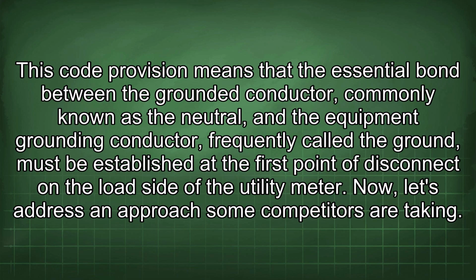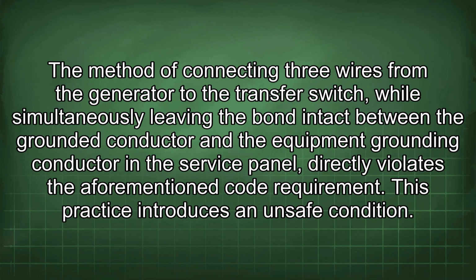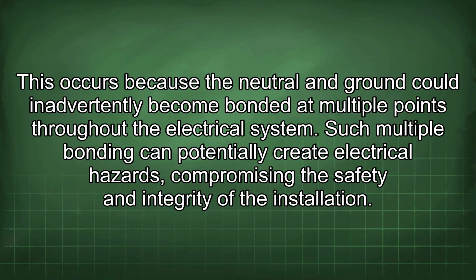Now let's address an approach some competitors are taking. The method of connecting 3 wires from the generator to the transfer switch, while simultaneously leaving the bond intact between the grounded conductor and the equipment grounding conductor in the service panel, directly violates the aforementioned code requirement. This practice introduces an unsafe condition. This occurs because the neutral and ground could inadvertently become bonded at multiple points throughout the electrical system. Such multiple bonding can potentially create electrical hazards, compromising the safety and integrity of the installation.